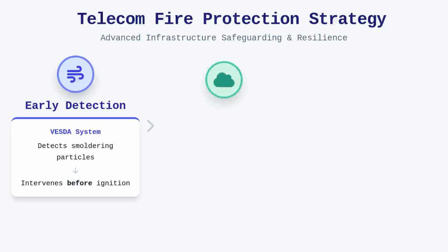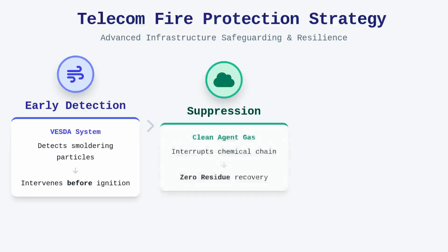When protection of the equipment is paramount, we turn to clean agent fire suppression, which uses specialized gaseous chemicals that absorb heat or interrupt the chemical chain reaction of fire. These systems are designed to reach a concentration level that suppresses the fire completely without leaving any residue, thereby allowing the equipment to remain operational or be brought back online quickly.